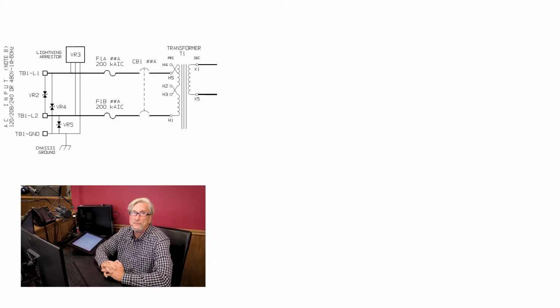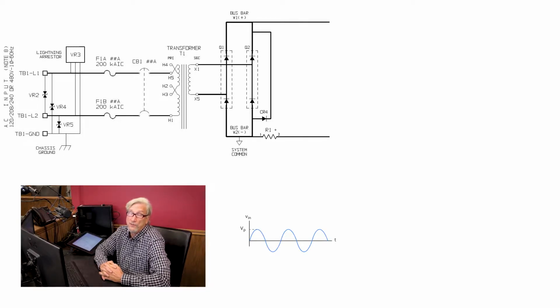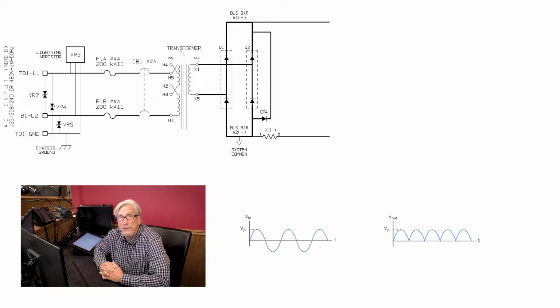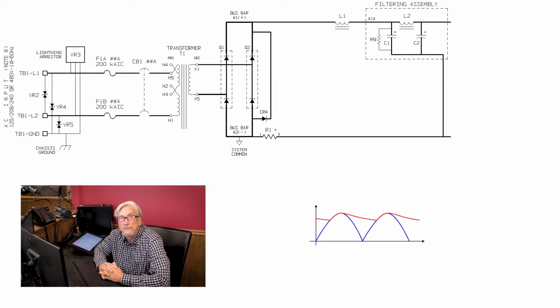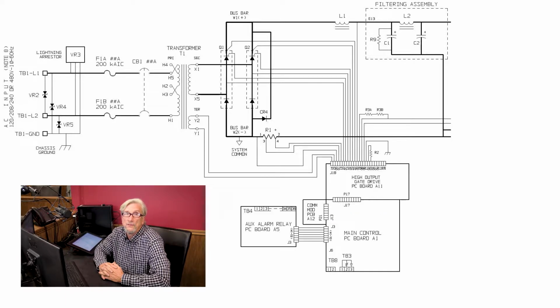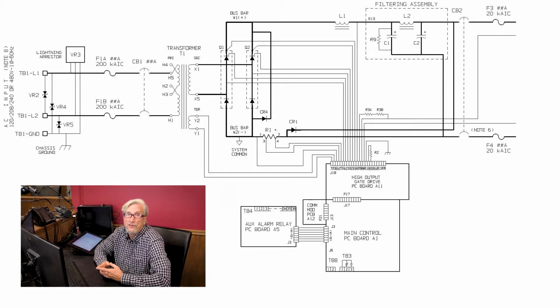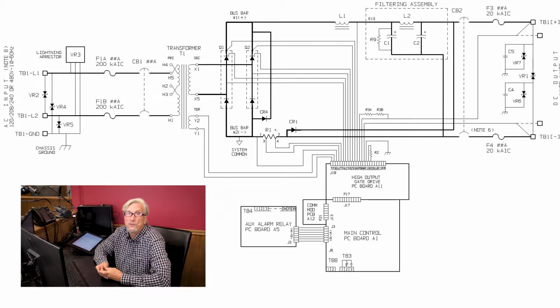After that, we go into an SCR bridge, and in the SCR bridge we convert the AC from the secondary to the output of the bridge, which is now DC. The next place it goes is a filter network, which includes an inductor, capacitors, other inductors, other capacitors, depending on how well filtered the charger is. Then something measures the output and brings it back to a control board, which controls the phase angle of the SCRs. This gives us accurate output voltage regulation and controls the output current. Once it leaves there, it goes to a device that protects the DC, and then to the output terminals where the customer connects the battery.